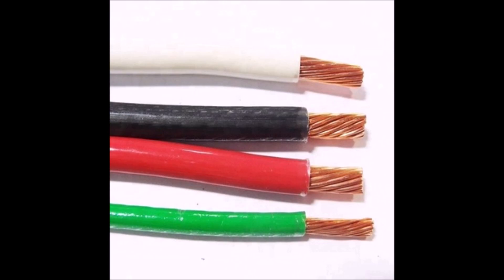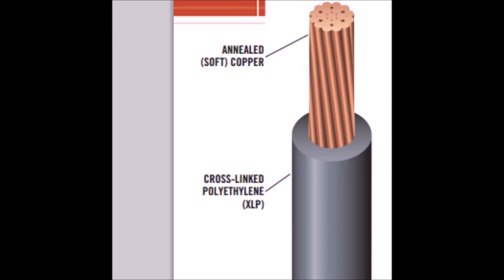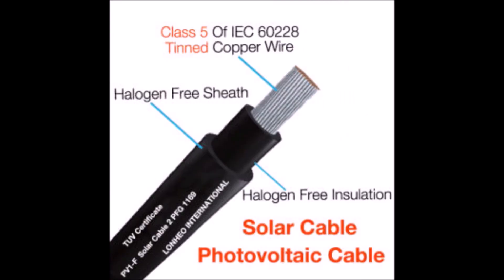For wire exposed to the elements, such as underneath your solar panels, you can choose USE2 or RHW2 cables, but there's also a specific rating for solar, called PV wire, that's the best for your system. This is especially true for off-grid systems, as PV wire is the best for ungrounded systems.